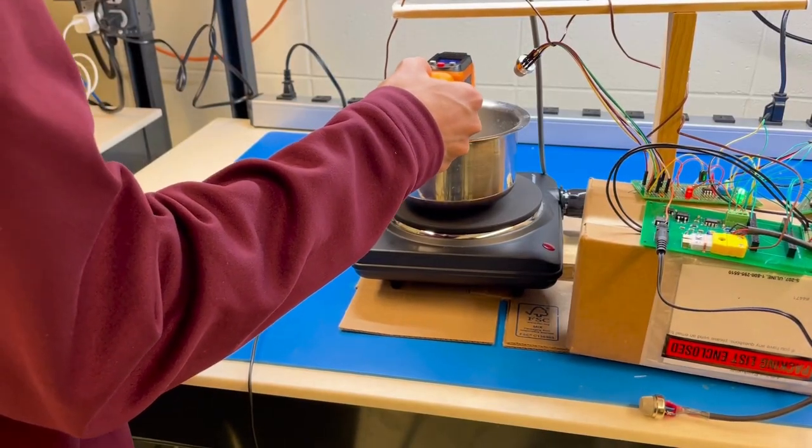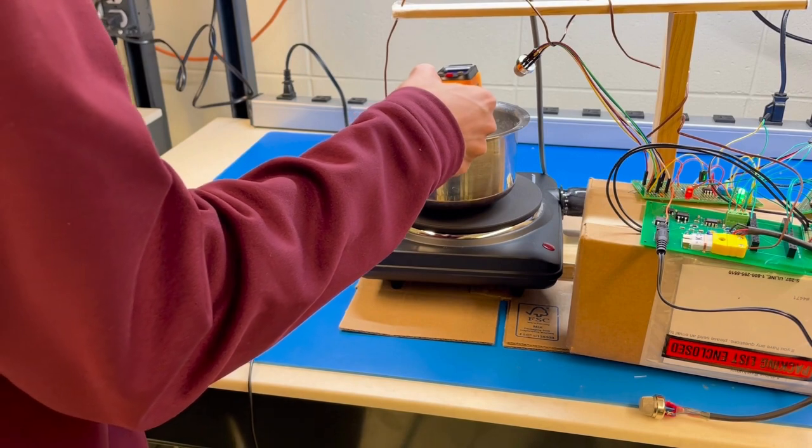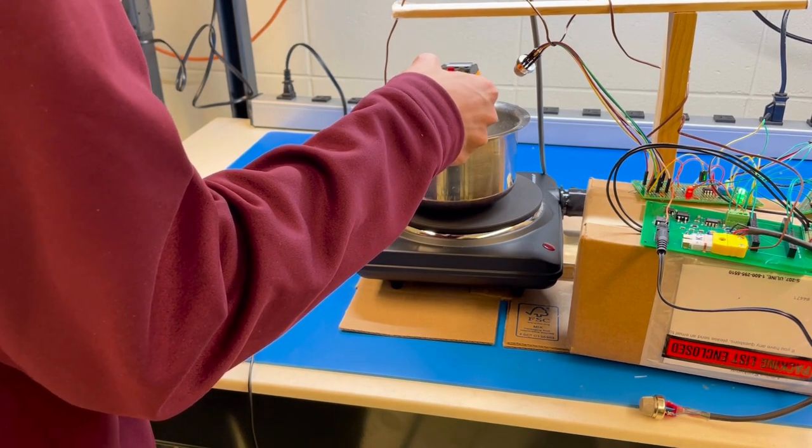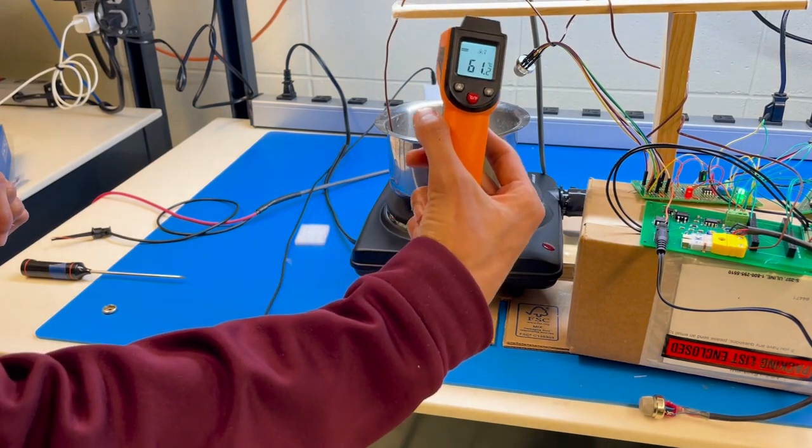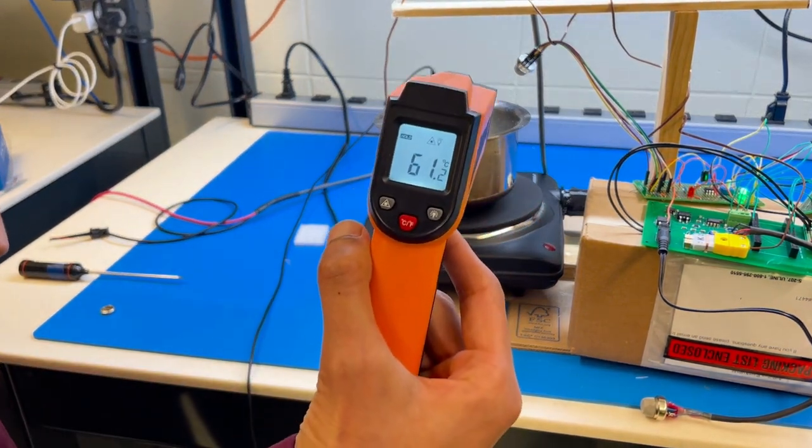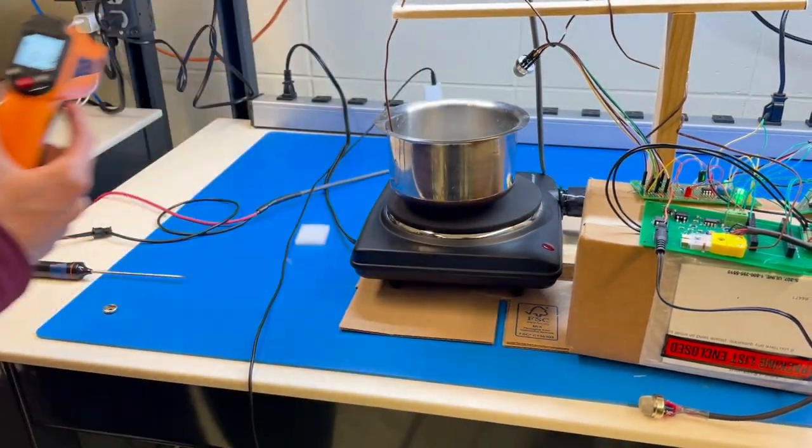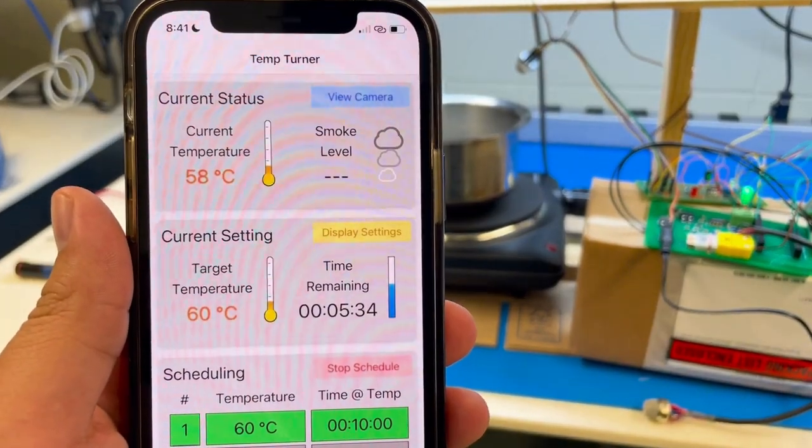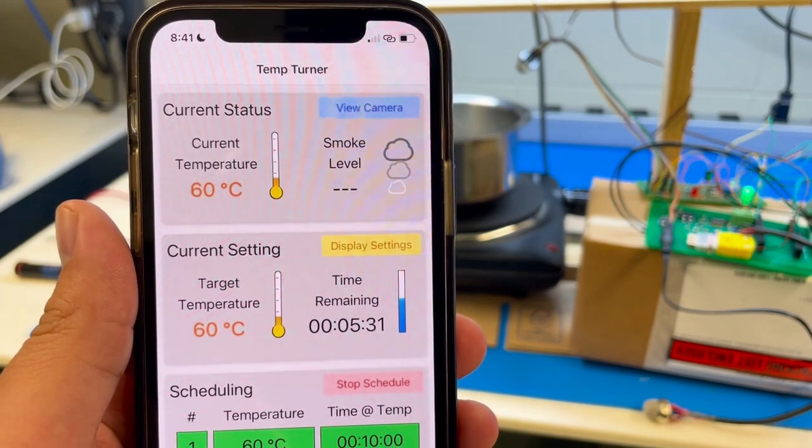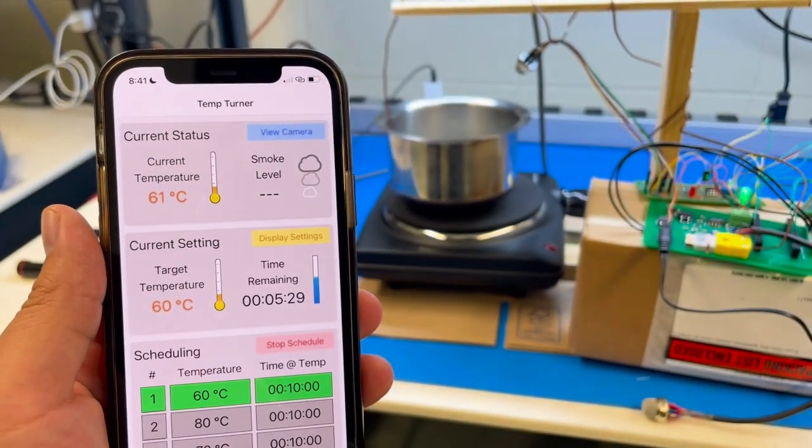Now let's check in on the water as it approaches 60 degrees Celsius. The IR thermometer shows a reading of 61 degrees Celsius. Let's see what the app shows now. The app also shows 61 degrees Celsius, as you just saw.